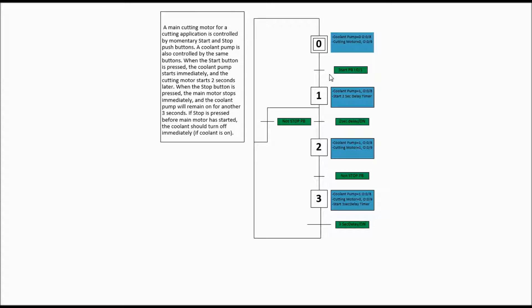Nothing is going to happen until a transition. The transition is when the start button is pressed. When that happens, the coolant pump is going to be equal to 1, and you're going to start a 2-second delay timer. If someone happens to press the normally closed wired stop button before the timer completes, it will return back to step 0.